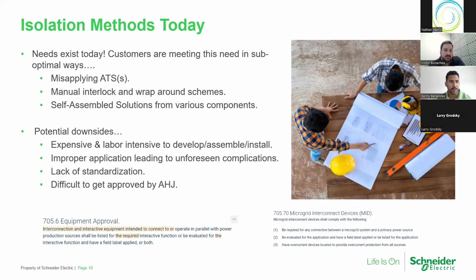And with this, there's an equipment approval listing within the National Electric Code that interconnection and interactive equipment must be connected to or operated in parallel with the primary production sources and must be able to disconnect and bring on alternative power sources to the system. So there needs to be a product that's tested to safely isolate from the primary source and connect to other alternate sources, which we accomplish. We reference it as an automatic interconnection switch. The National Electric Code references it as a microgrid interconnect device. The two are interchangeable, but that is the approved product that we're looking for today. It's the microgrid interconnect device.